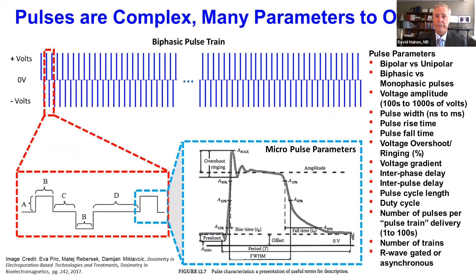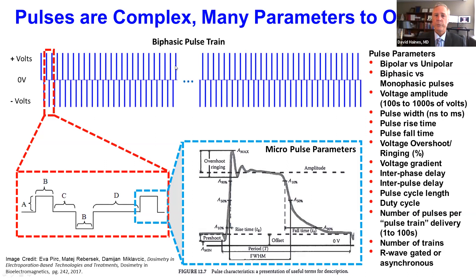Pulsed field ablation, unlike RF, has many parameters to be considered. Each particular pulse has a variety of things that can be modulated, and each pulse can be put together in a train, can be monophasic or biphasic. The pulse width, amplitude, train number, and interpulse distance — all of these things can be adjusted. The question is: what's important and what translates into safe and effective ablation?